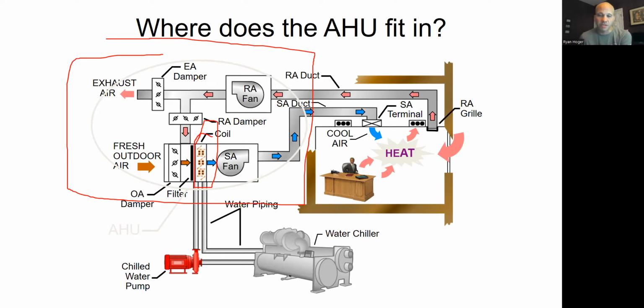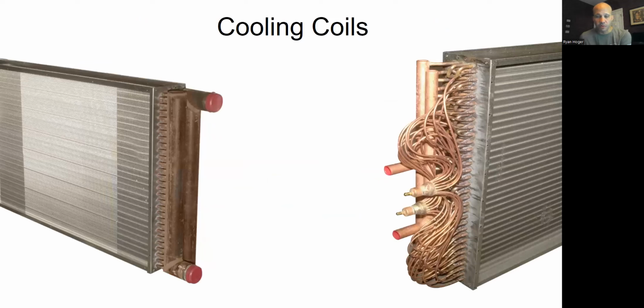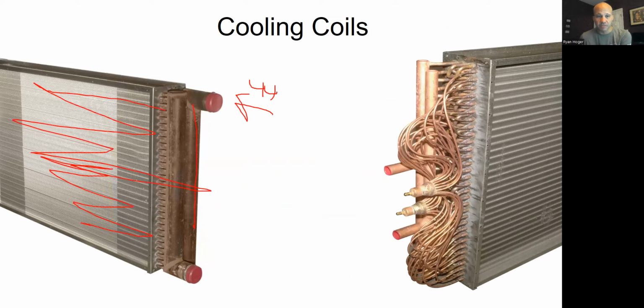Or it's going to be a DX coil, meaning it has refrigerant in it. So just like before, we said you can look at the coil to figure that out. If it's chilled water, the water will come in, like we said, typically at 44 degrees. It'll flood this header, send water up and down the coil, up and down the coil, up and down the coil, all these different rows, and go back to the return header and leave at 56.